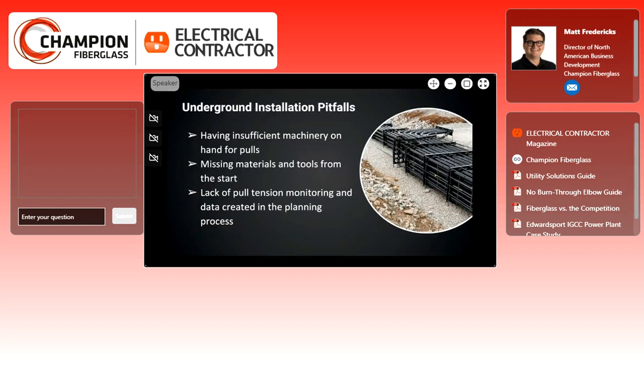The lack of pull tension monitoring and data from the pulling process can be a real liability. Many cable manufacturers now require pull data for their warranties. They put a lot of time and effort into engineering their cable to be as robust as possible, but there are certain limits on sidewall pressure for pulling. Using the software I mentioned earlier is very helpful, and having real-time pulling tension monitoring is important too.